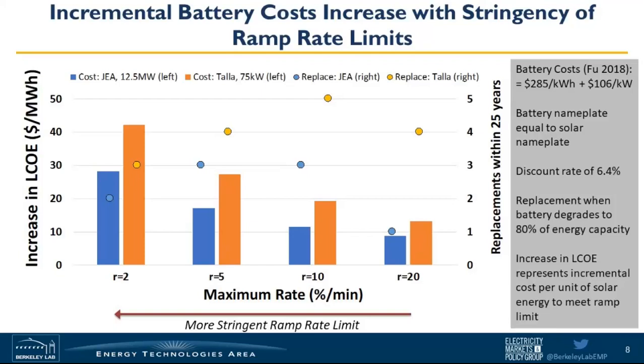The results here show that the ramp rate limits with storage could easily increase the costs by more than $10 per megawatt hour of solar. One final note is that we compared the results from 2 different PV plants. We have one small 75 kilowatt plant and one large 12.5 megawatt plant. The larger plant results are shown here in the blue.